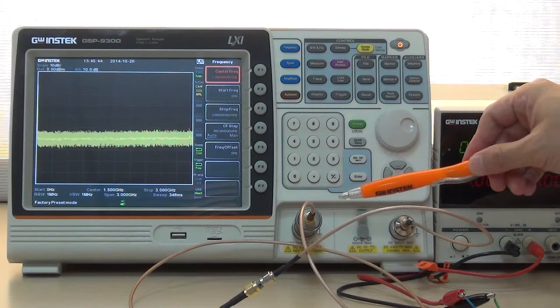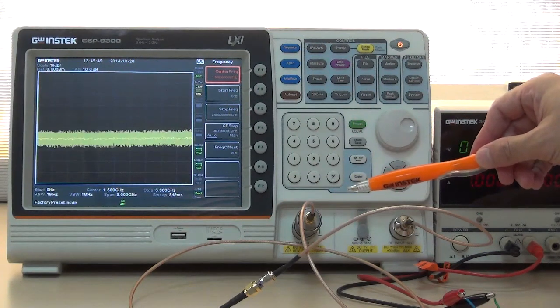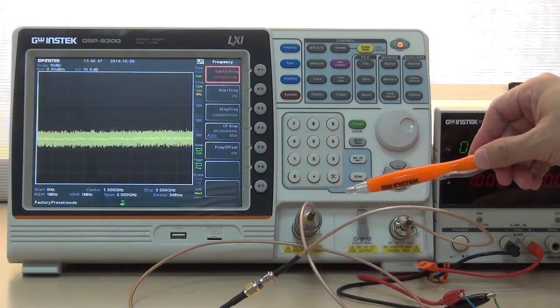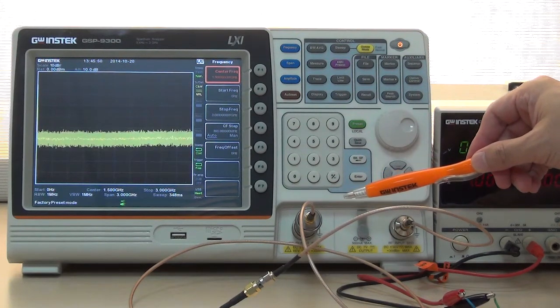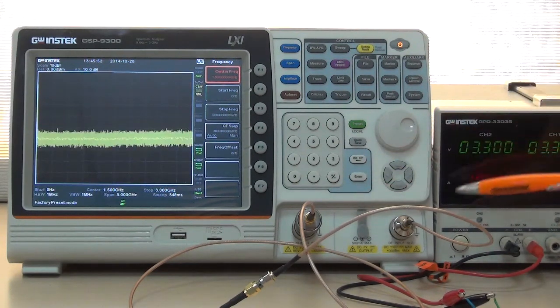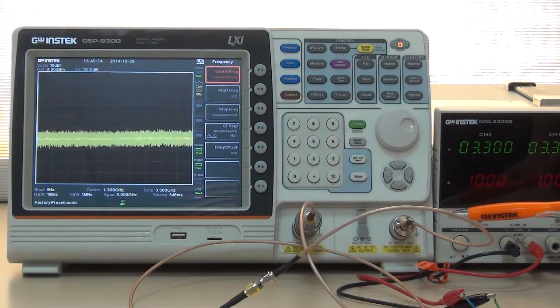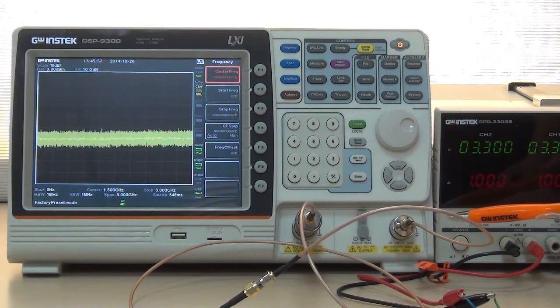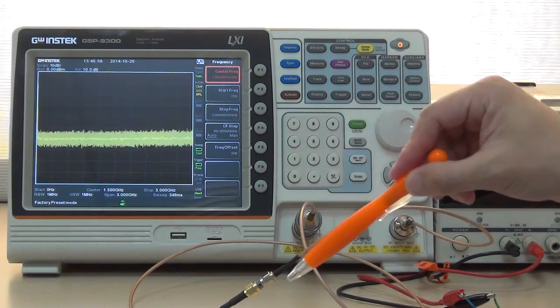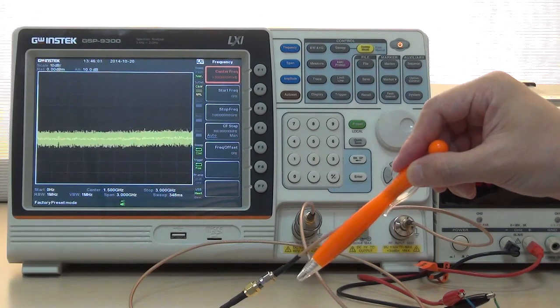First of all, connect 10 dB attenuator and SMA RF cable with tracking generator output. Connect RF input of GSP9300 with SMA RF cable and connect both ends with SMA RF cable.